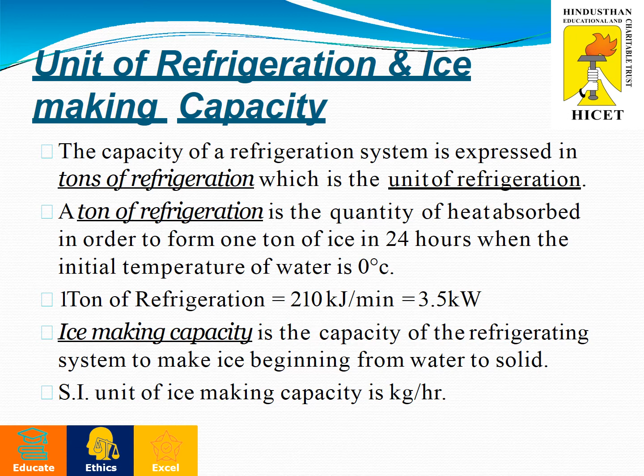In the equation, 1 ton of refrigeration equals 210 kilojoules per minute. Joules per second is watts, so in kilowatts we can say 3.5 kilowatts. This is the standard unit for 1 ton. Ice making capacity is the capacity of a refrigerating system to make ice from water to solid. In SI units, the ice making capacity is in kilograms per hour. These are the units for refrigeration.